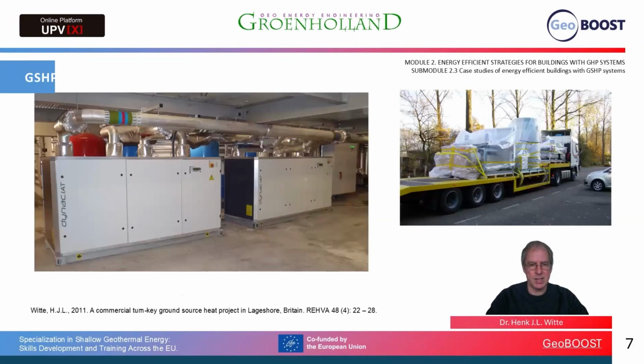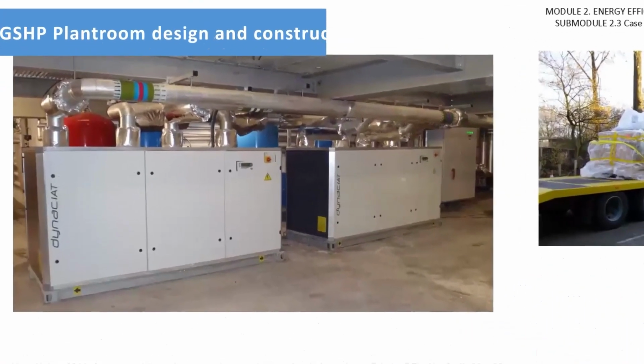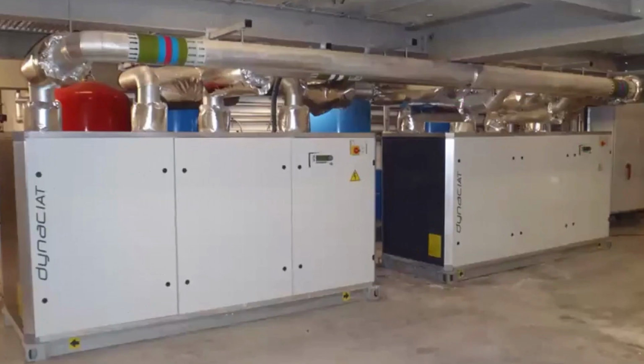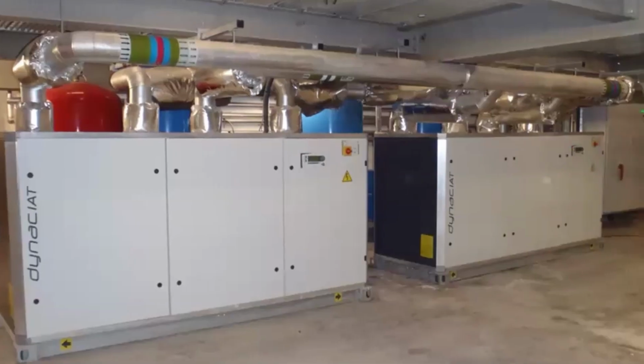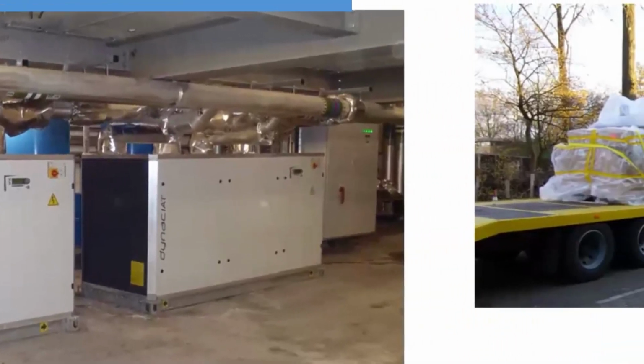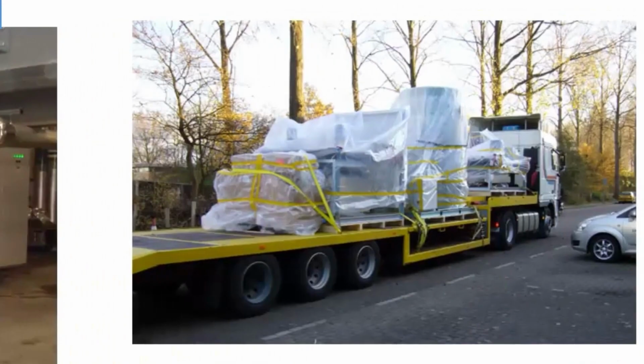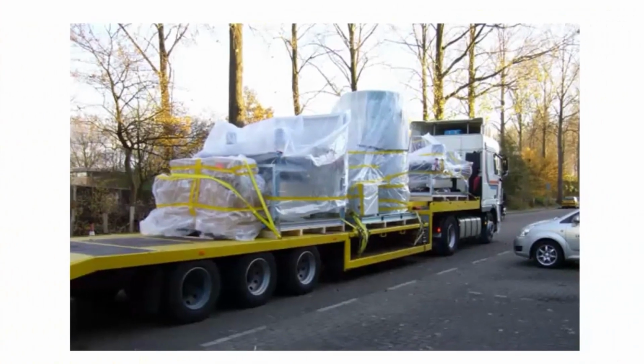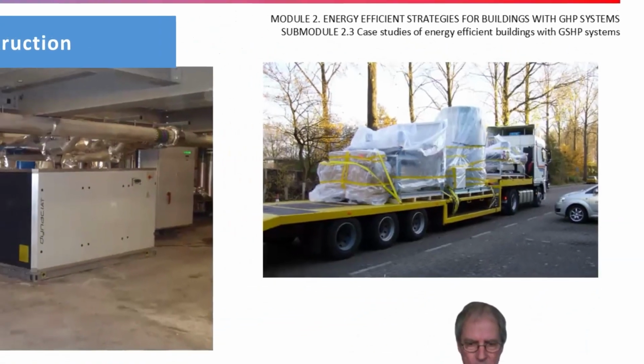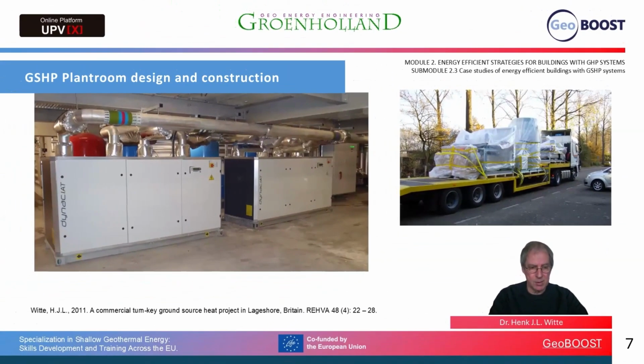The actual plant looks like this with 2 4-compressor heat pumps. So each heat pump has 4 compressors in total. The total system is 8 compressors. They're all on-off compressors. So we have a fairly good match with part load conditions. On the right, you can see, the whole system was built on skids in Amsterdam and delivered to site on a lorry. It's been running well since it was installed, and if you want to know more about it, there is a paper published in the REHVA Journal 48 in 2011.